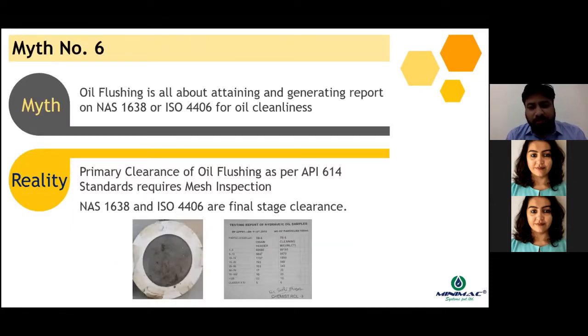As per our experience around oil flushing, we do honor the two standards of NAS 1638 and ISO 4406 for checking the quality of fluid being used for the oil flushing activity. That's one of the major tests and milestones which every oil flushing professional must follow. But at the same time, we would like to address a very important parameter which one needs to inspect properly, and that's mentioned in the API 614 standard. The test is called mesh inspection. You can see the mesh photograph down there, and you can also compare the results.